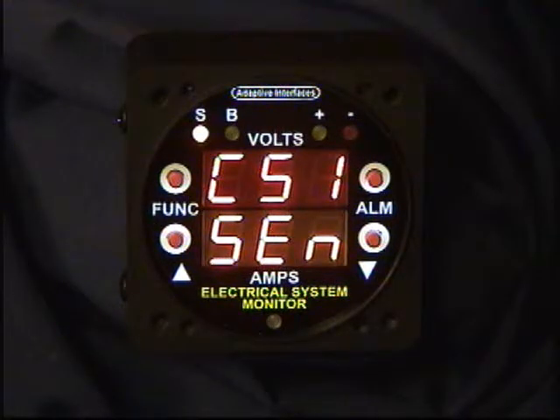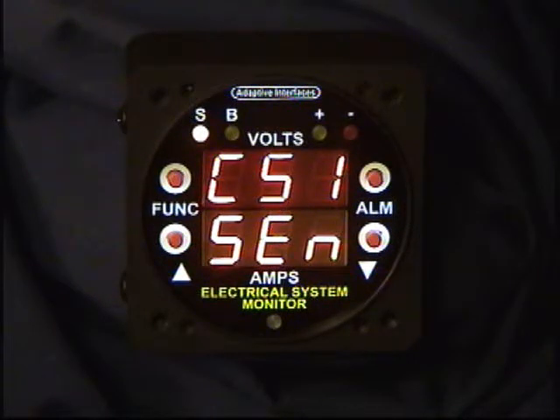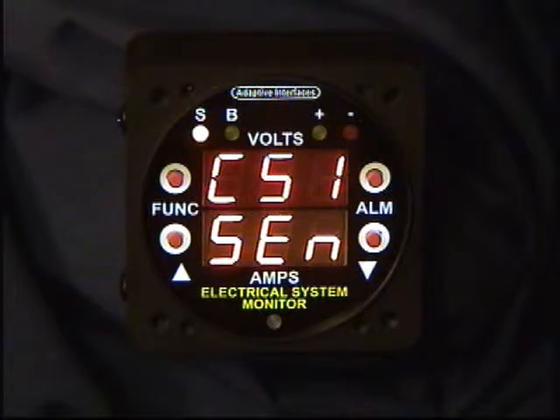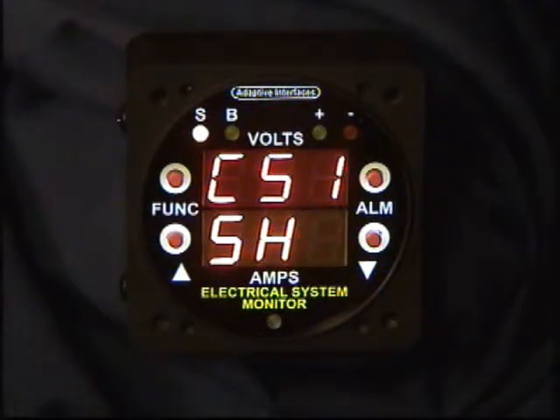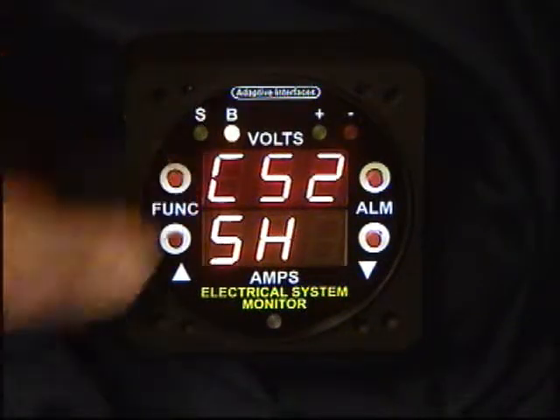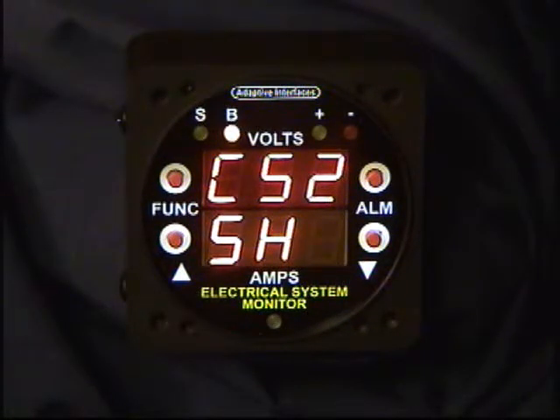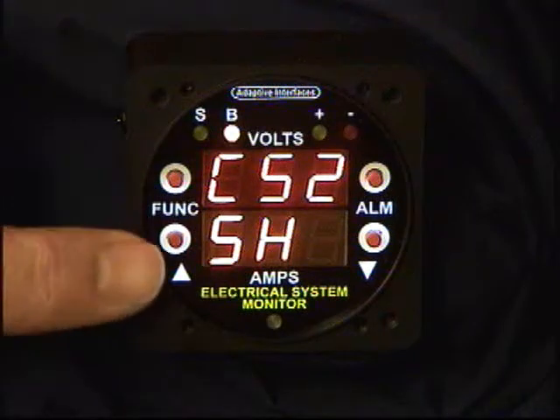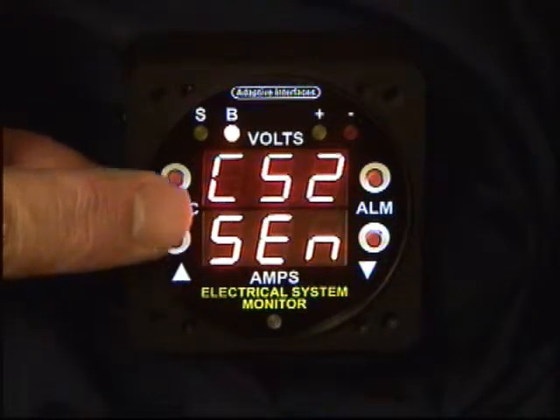The next function is the selection of the type of current sensor for current sensor 1, the system current sensor. Two types can be used: a Hall effect sensor, which is currently selected, or a standard 50 millivolt current shunt. The next function is the sensor type selection for current sensor 2, the battery current sensor. Right now it's set for a shunt, but it can also be selected as a Hall effect sensor.